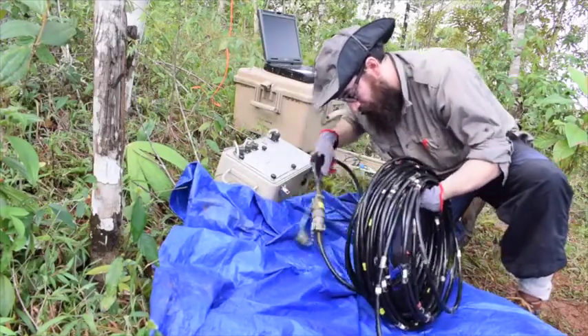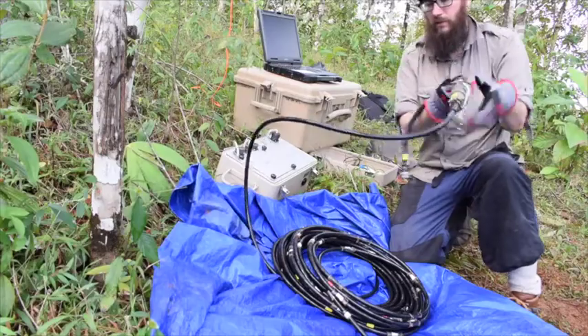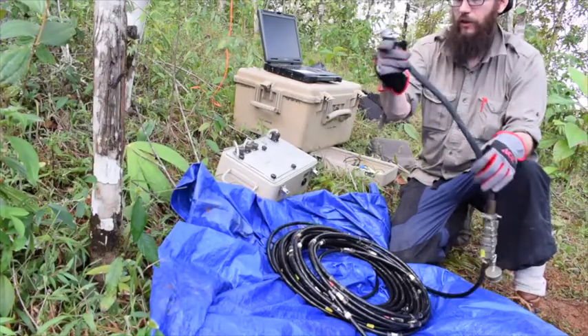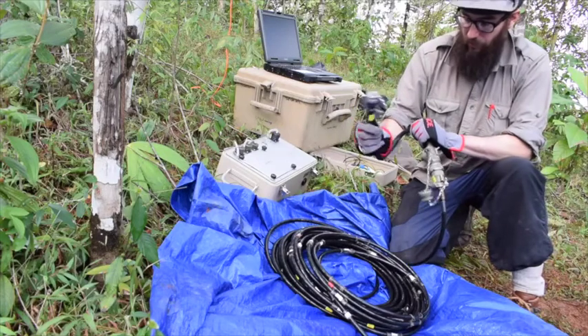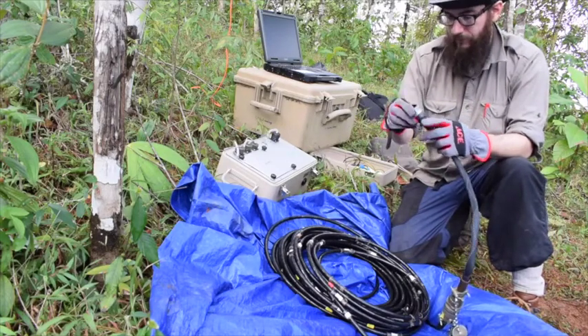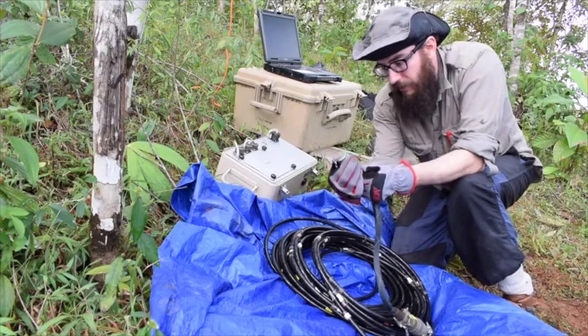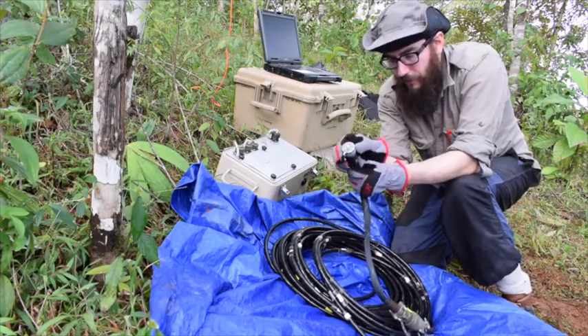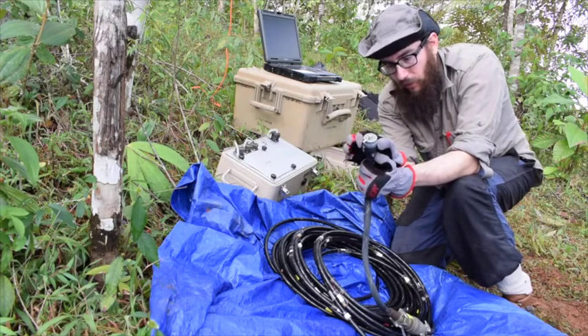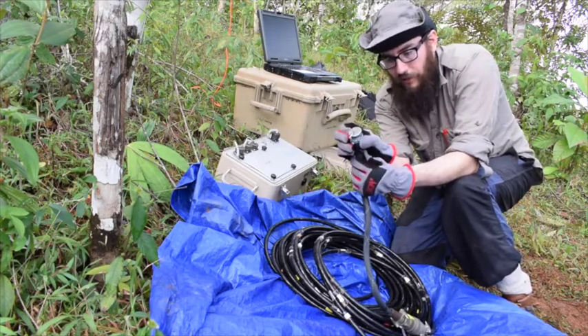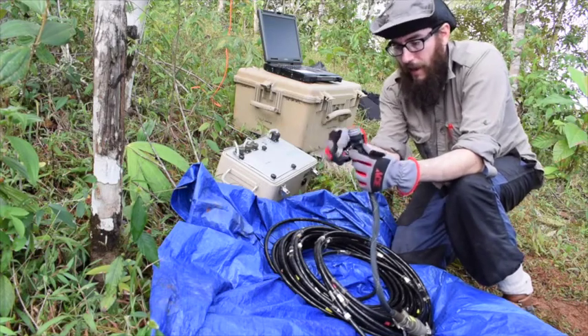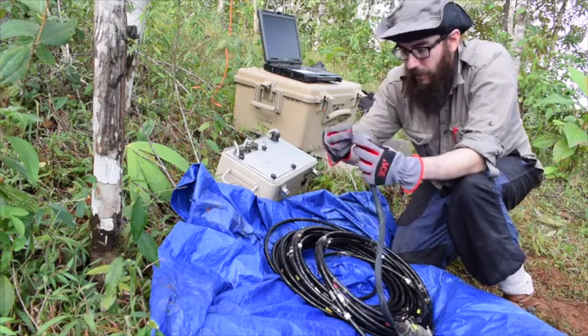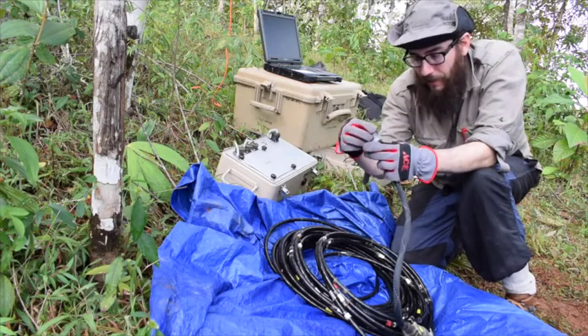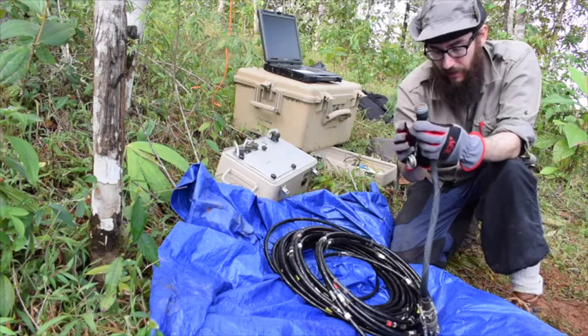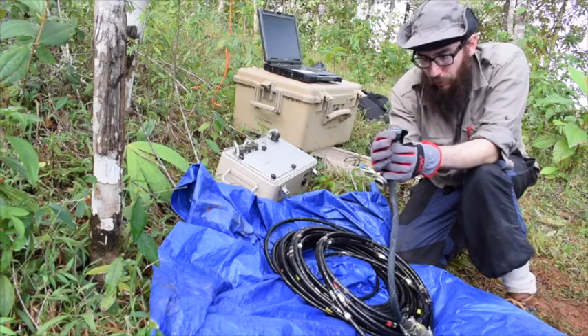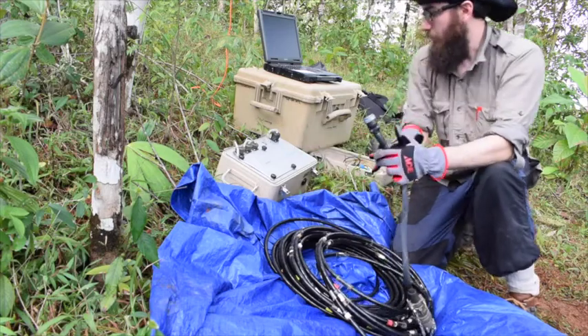all you need is maybe a meter or so at the end, and you're looking for the floppier part of the cable with the little extra connectors. And so these are the Milspec Amphenol connectors, and it's a little bit counterintuitive. You actually put your fingers on the barrel below the top of the gap, so below the blue line, and just spin the bottom part of the barrel and the top pops off. If you try to just twist the little top cap, it won't ever come, and that's actually an easy way to break it. So what you need to do is just grab below the blue line and spin that, and the top will just jump right off.